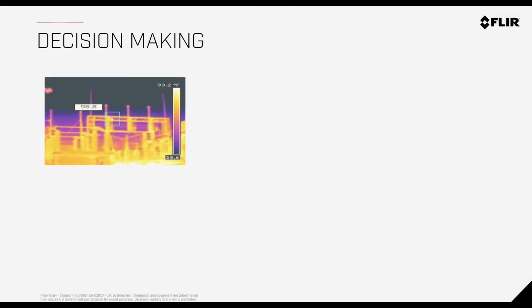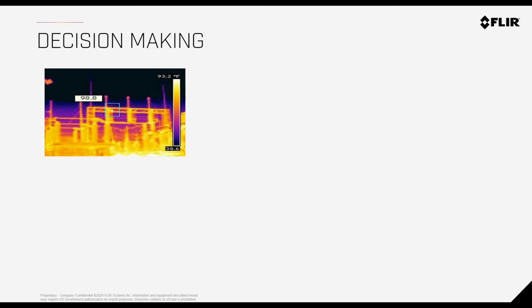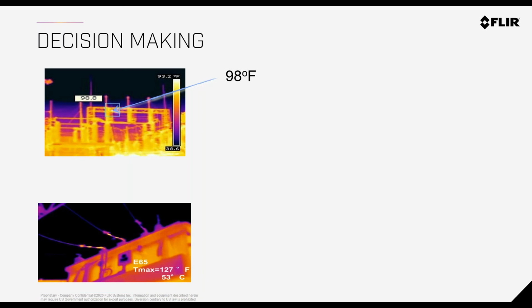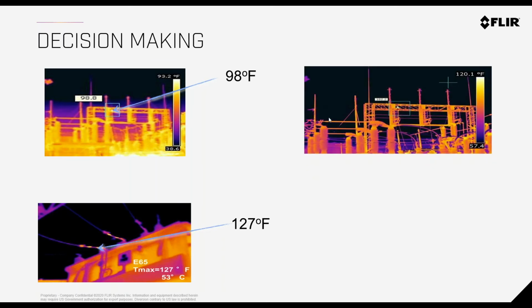These thermal cameras are going to help you with decision making. Again, the stronger the camera, generally, the better the performance and the better the decision making that you're going to get. When we look at these two images, we can see that the hottest spot in this box is 98 degrees, or on this line the hottest spot is 127 degrees. Now, when we take the same image with a higher powered camera, we can see that actually that spot is 182 degrees. So now we have more pixels on this target. That's going to give us more temperature readings, and it's going to give us more accuracy, because now we have smaller pixels on that target to give us the actual reading.